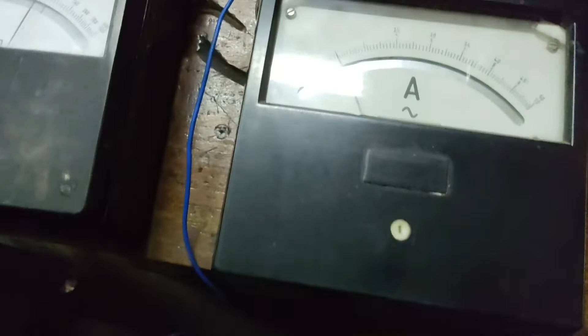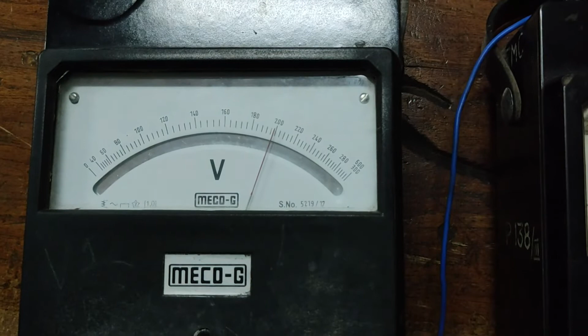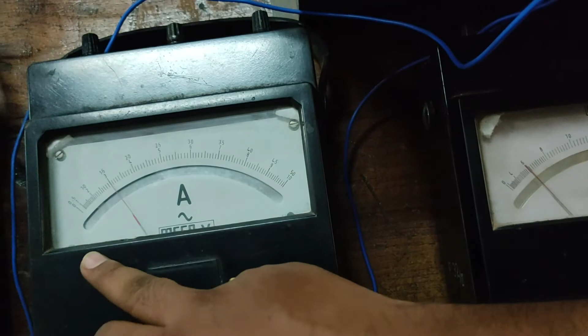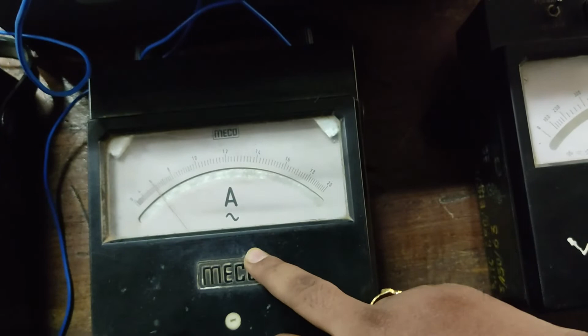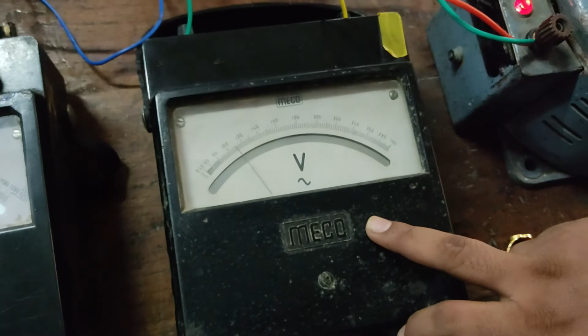That's all. Suppose you go for one more reading, please sir, wait. Just turn on one more load. Yes. Now there are changes on the load side ammeter. There is a drop in the load voltage because we are giving the resistive load. Compared to the previous reading the load current is increased because of the load, and this input side current is also increased from the previous load. The wattmeter reading also increased. This should be constant. That's all. Like this we can go up to the rated current of the transformer on the secondary side.